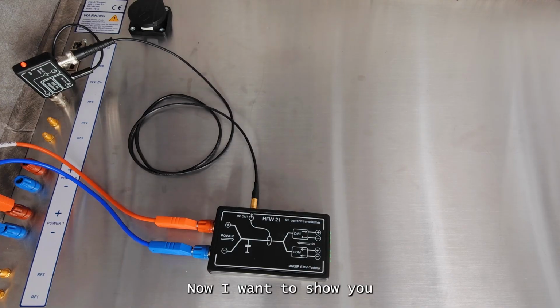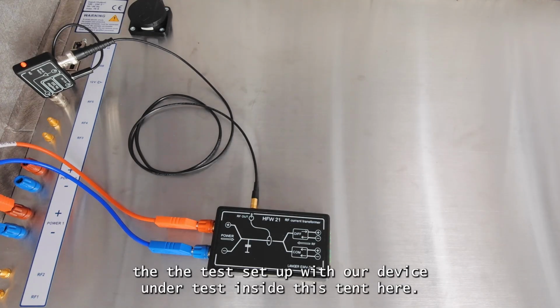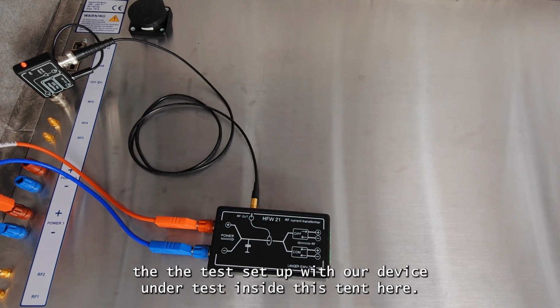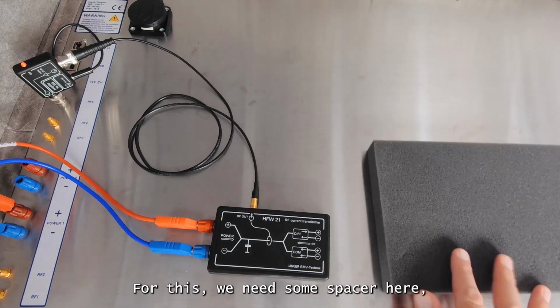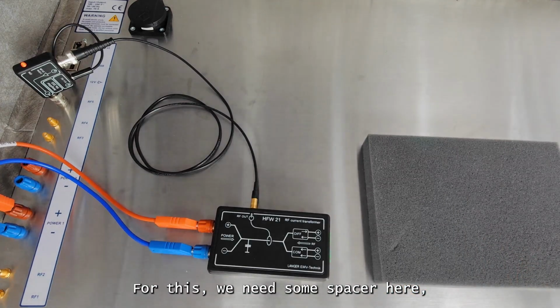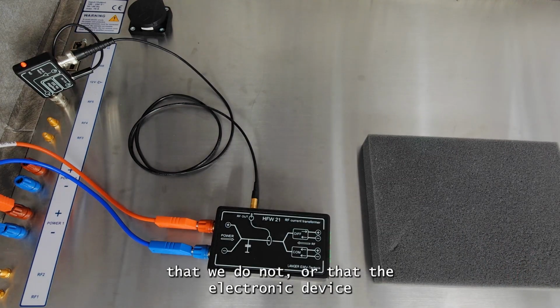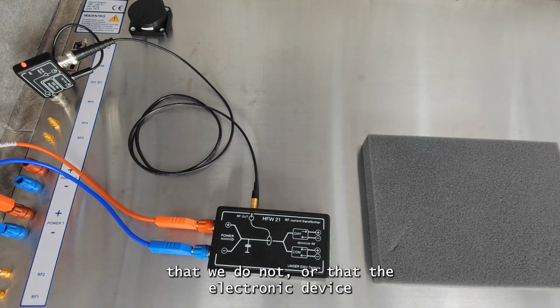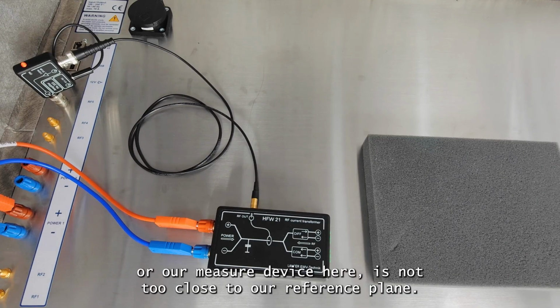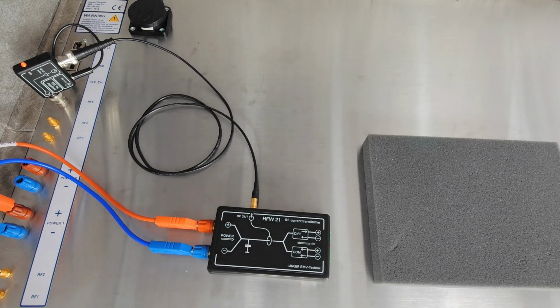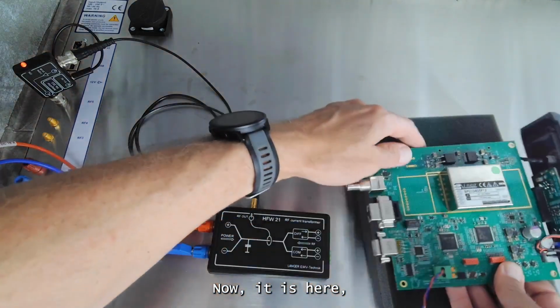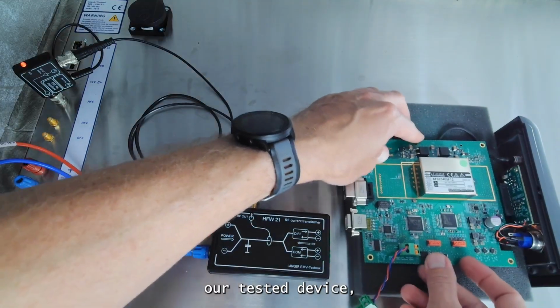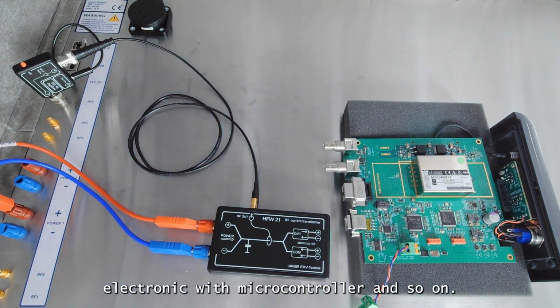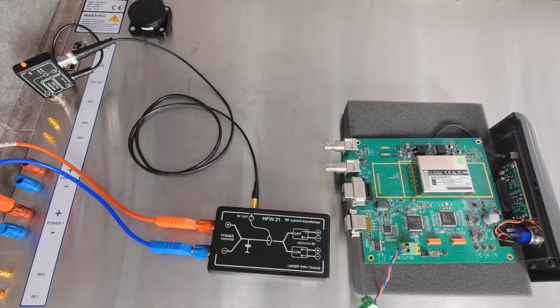Now I want to show you the test setup with our device under test inside this tent. For this we need some spacer so that the electronic device, our measured device, is not too close to our reference plane. Now this is our tested device, electronic with microcontroller and so on.